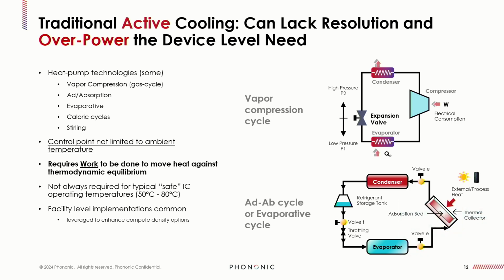At the facility level, we've long implemented the ability to merge active cooling technologies with passive cooling technologies - you've heard this many times today. You have air cooling, maybe water cooling at the rack or server level, and then that is coupled, whether by water or air, to a cooling system - chiller, tower, vapor compression, air cooling, you name it. We like all of these cycles because, again, we play very well with them, but the active cooling solutions tend to overpower a device level implementation.